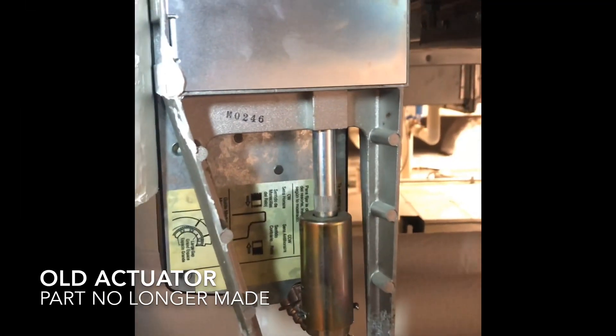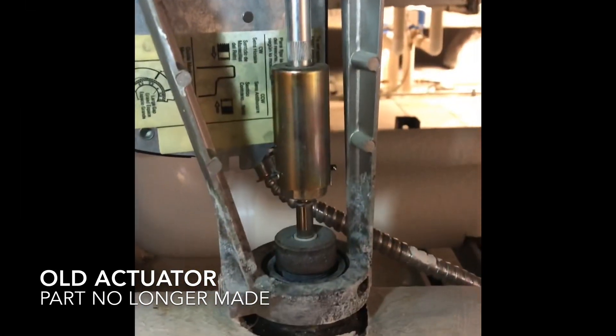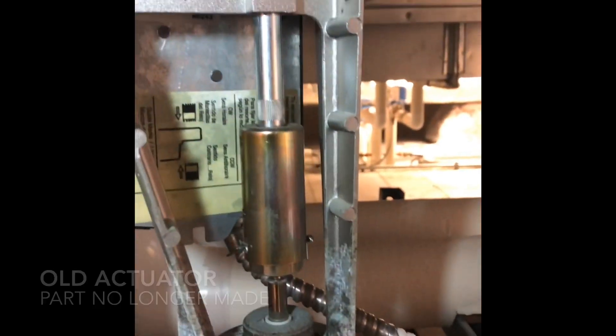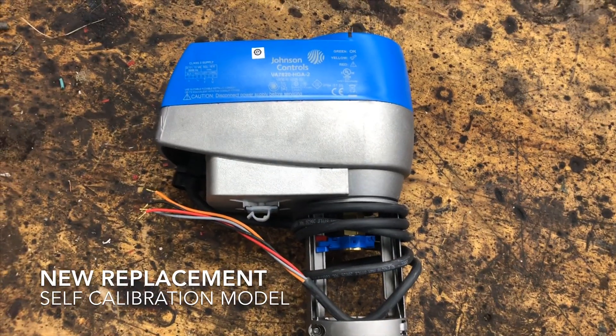Here we have a failed actuator assembly on a Johnson Controls three-way globe valve. It is stuck in the up position. Here's our new actuator.